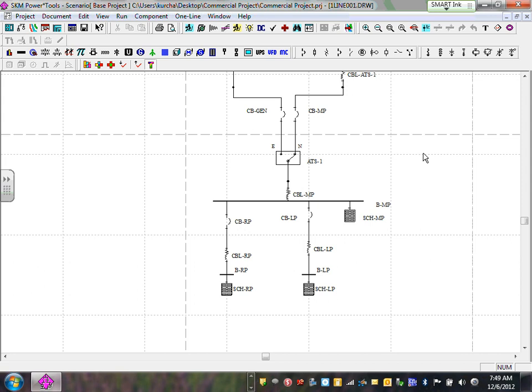Now, who am I going to pick on? Joe, my friend. When you do short circuit coordination, overcurrent protection coordination, the only circuit breakers you care about are the mains. That's it. Branch circuits, not a big deal. Only the mains that we worry about. Can I have thumbs up, Chad? We worry about the mains? Cool.